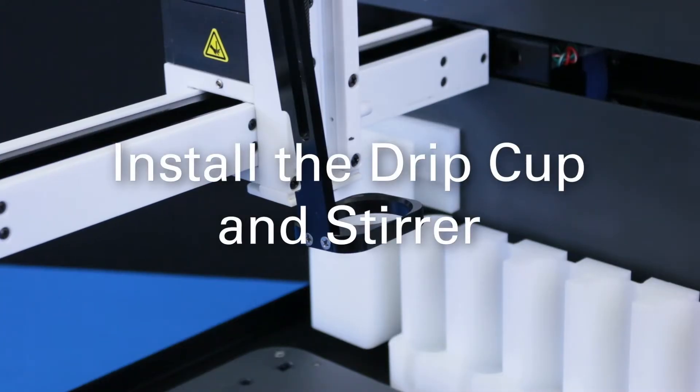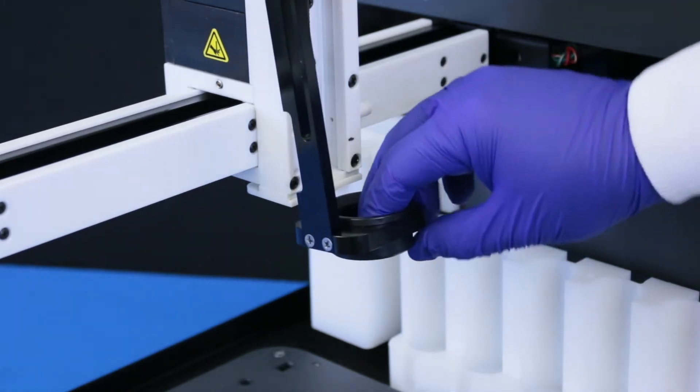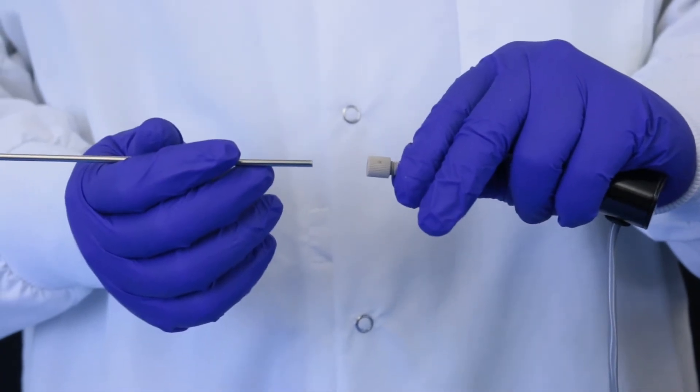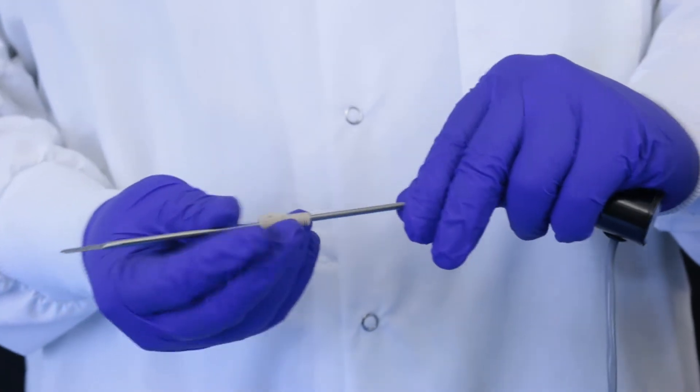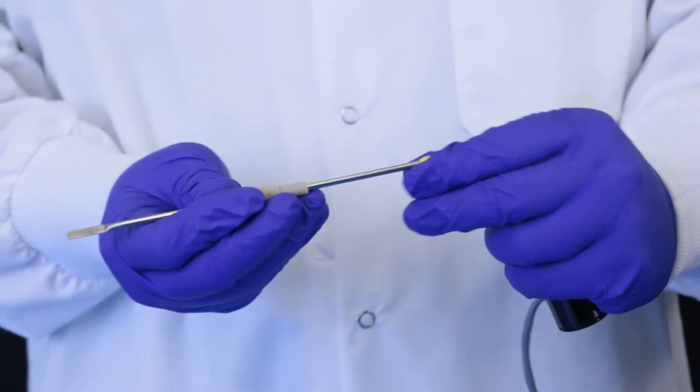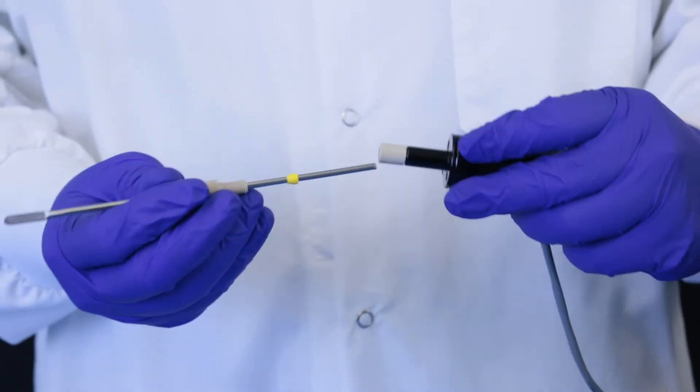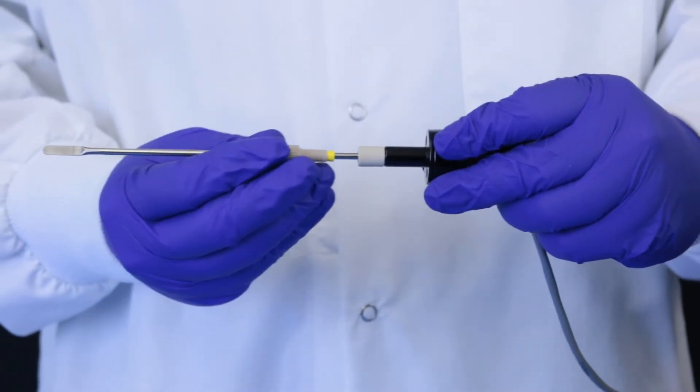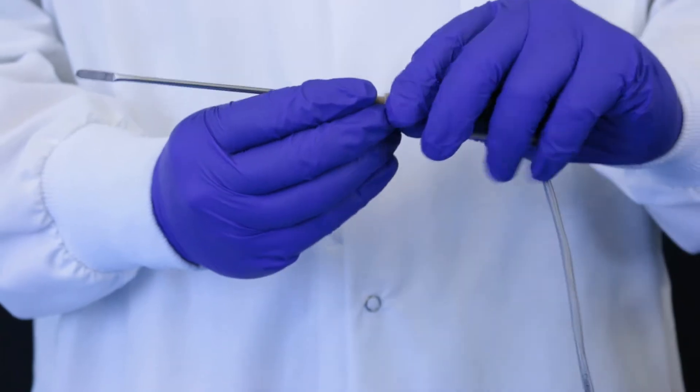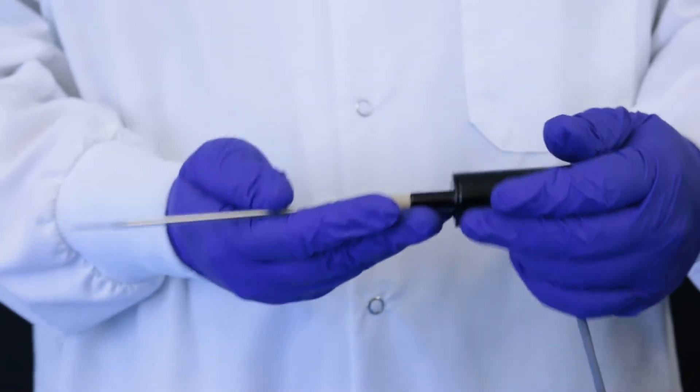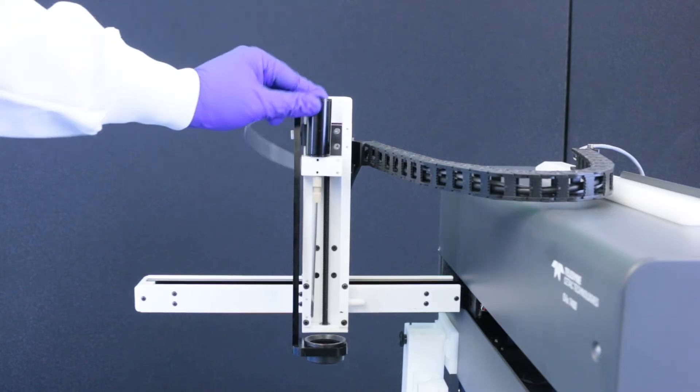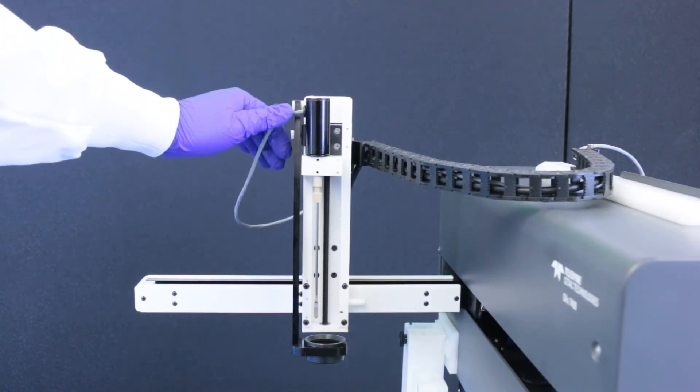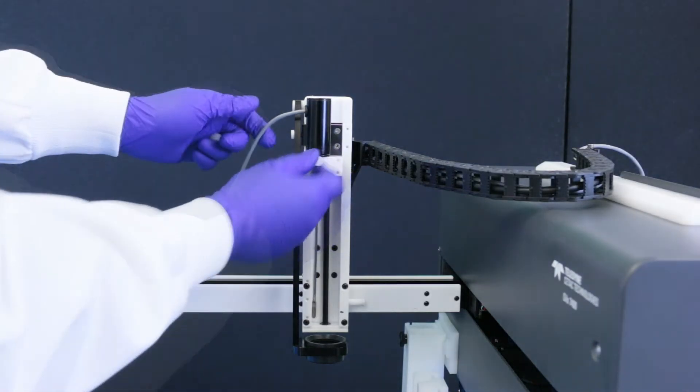Install the drip cup and stirrer. Press the drip cup into place. Locate the oil stirrer paddle. Place the nut and ferrule on the paddle. Press the stirrer paddle into the hole on the bottom of the stirrer motor. Place the stirrer motor into the larger hole in the probe stirrer block on the Z-Drive. Tighten the two thumb screws.